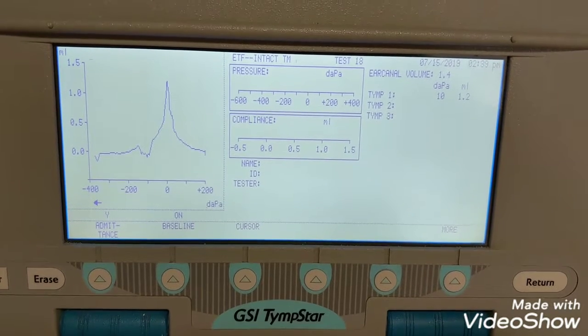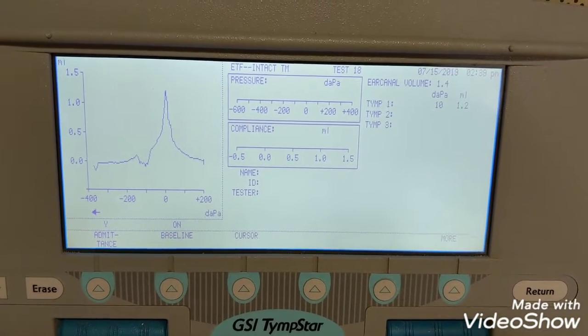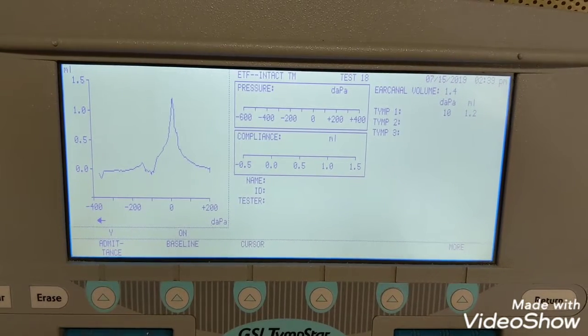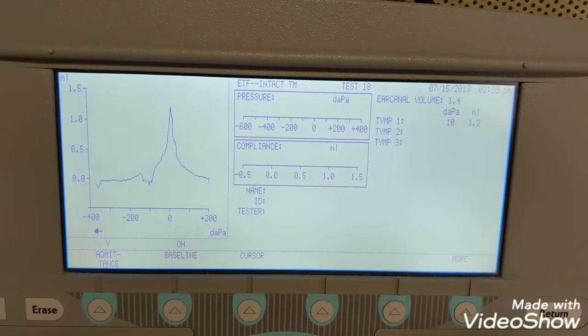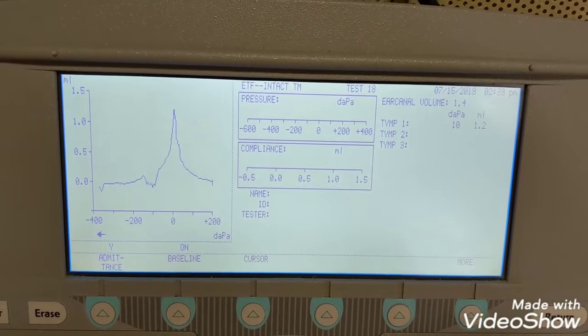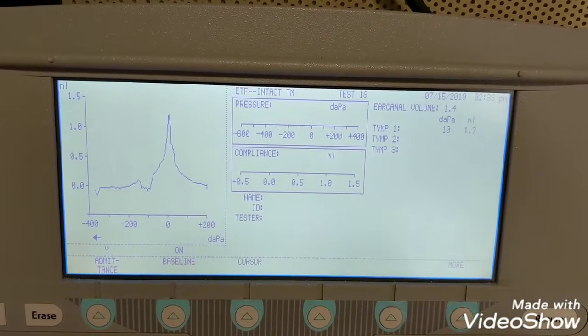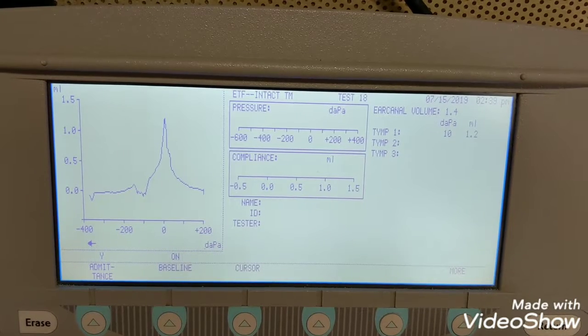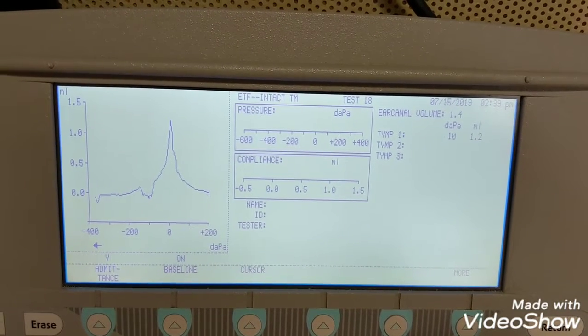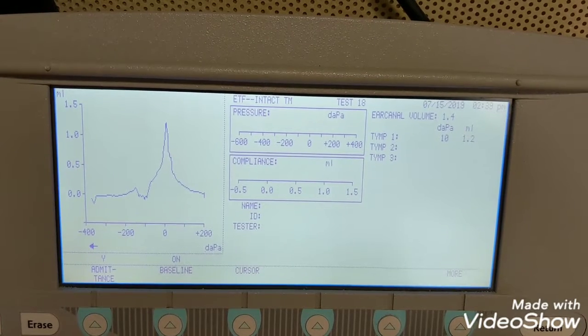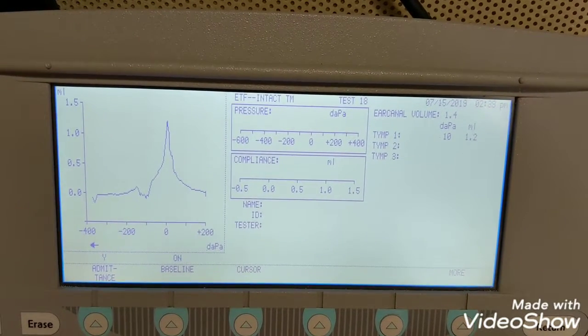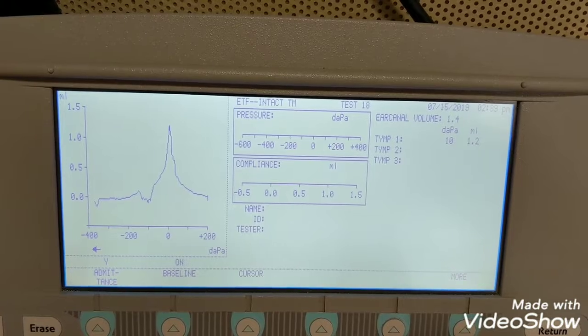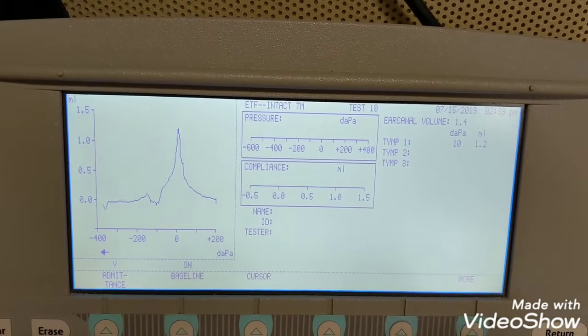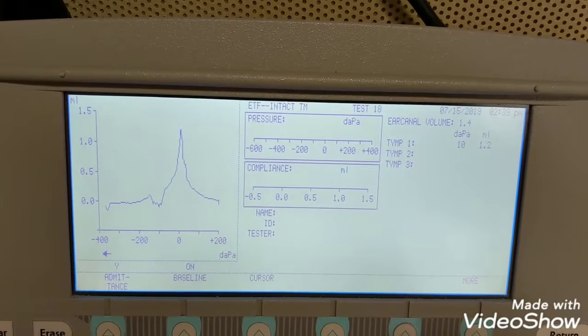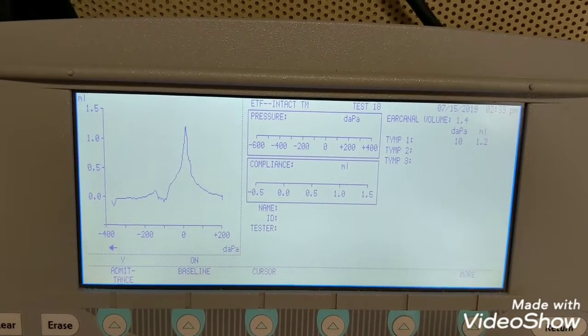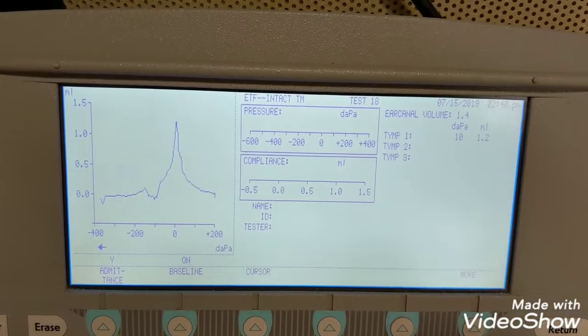The measurements are shown to the right side, where before in the other room they were along the bottom of the measurement. But if you look to the left, you can still see that it has that peak that comes up and then down, showing the maximum compliance of this eardrum to be 1.2 milliliters of H2O is what the measurement is. But my compliance, if you recall, was 0.44, I believe, and so this one is 1.2. That's significantly more. However, it's still within the normal range.